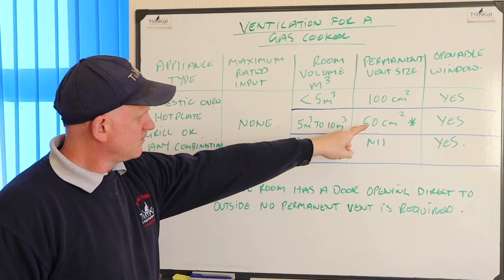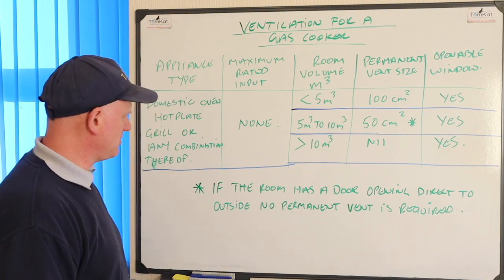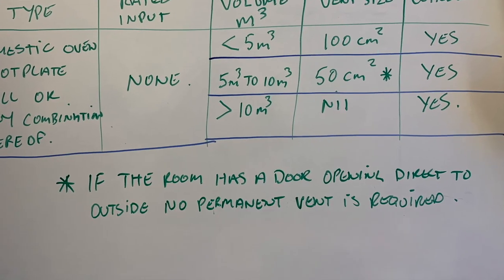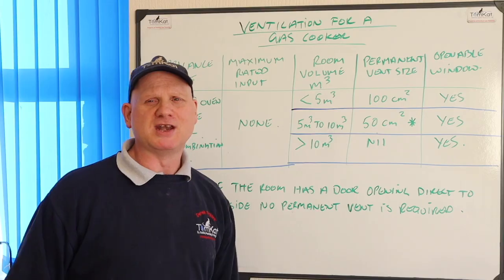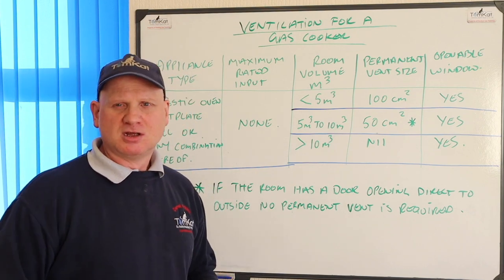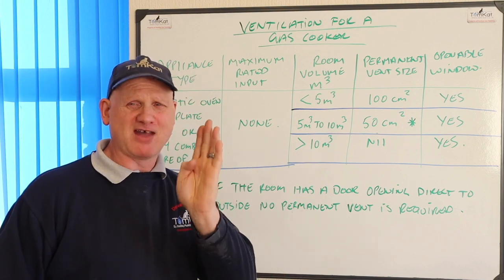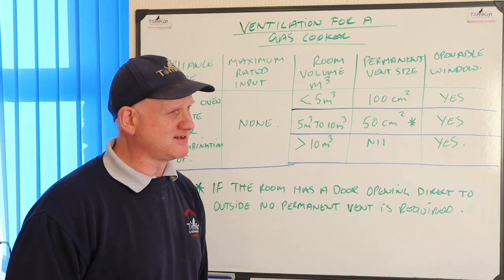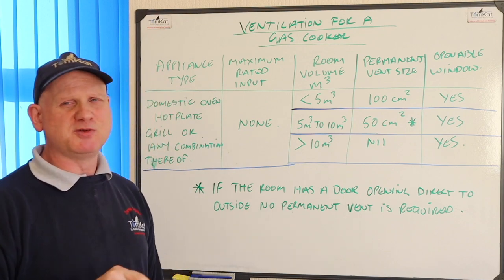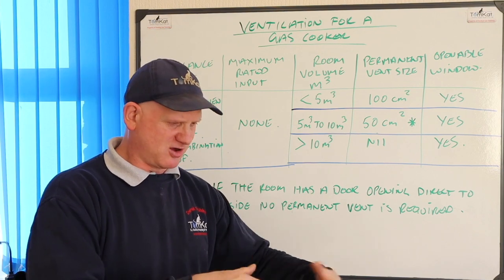If the room volume is between five and ten metres cubed and the room has a door opening directly to outside, no permanent vent is required, but the openable window still is — or any kind of extraction that complies to the building regs. If you have a bedsit, it has to be over 20 metres cubed before you can have a cooker in it; other than that you can only have a single ring or hot plate.